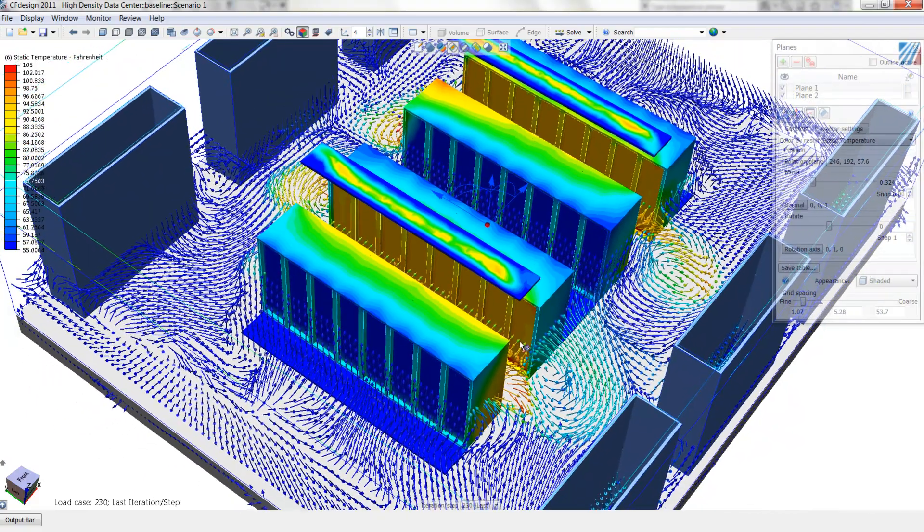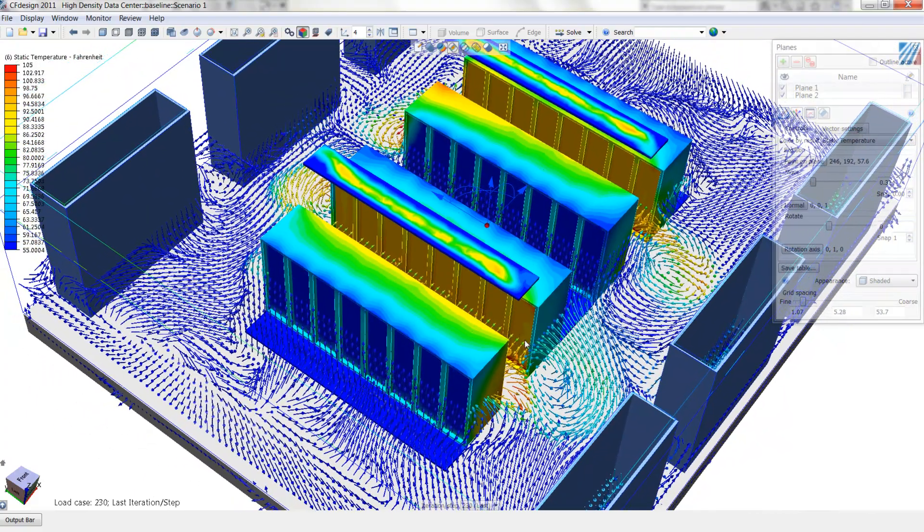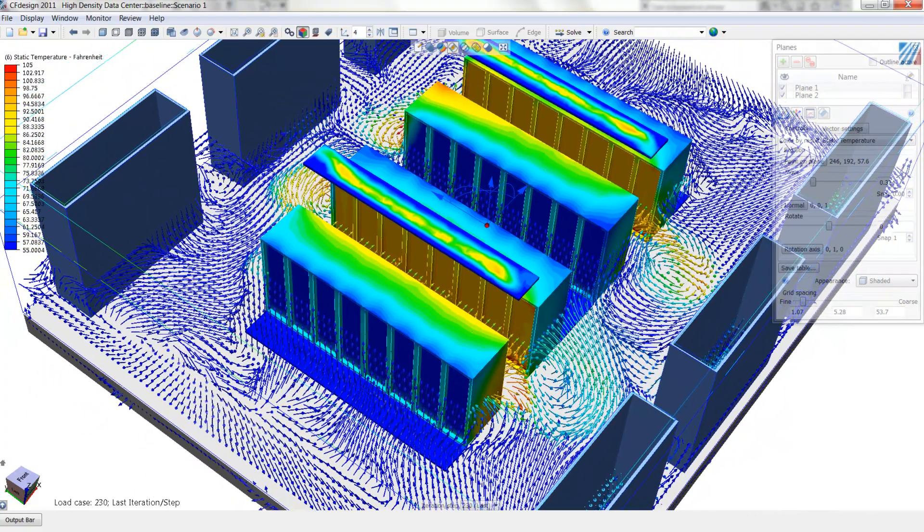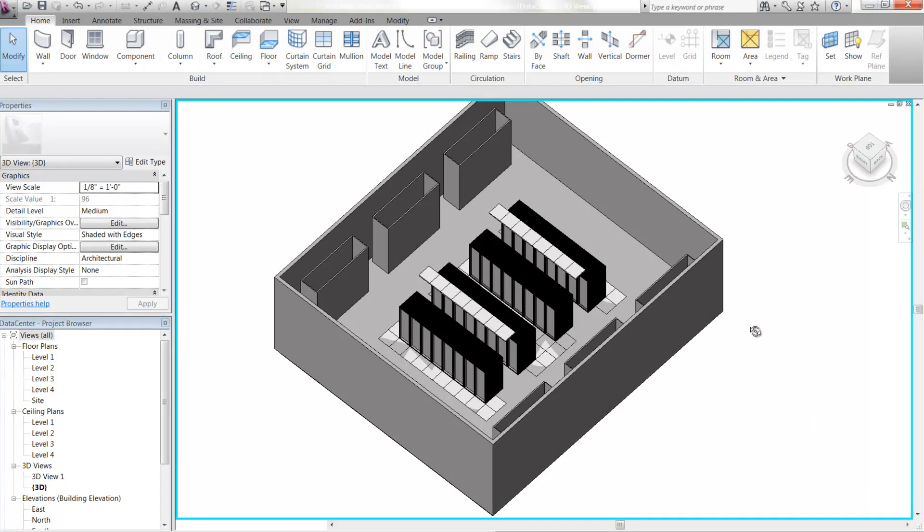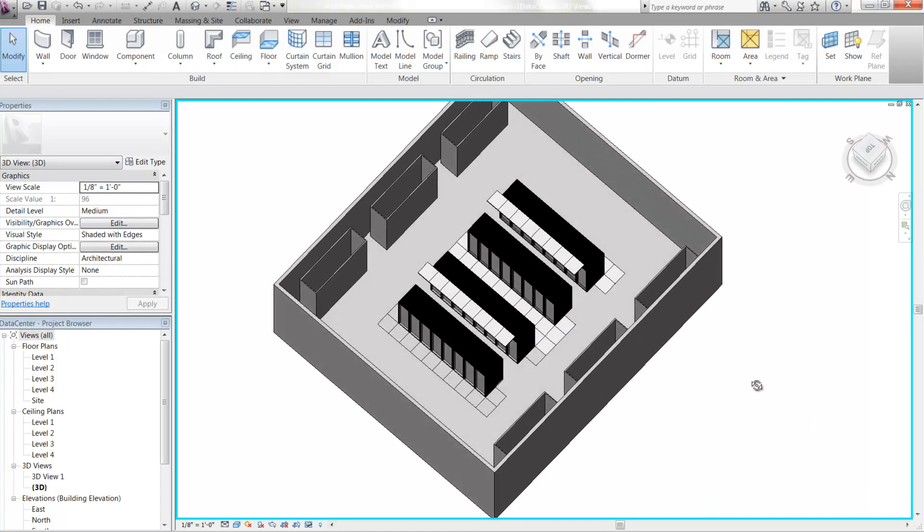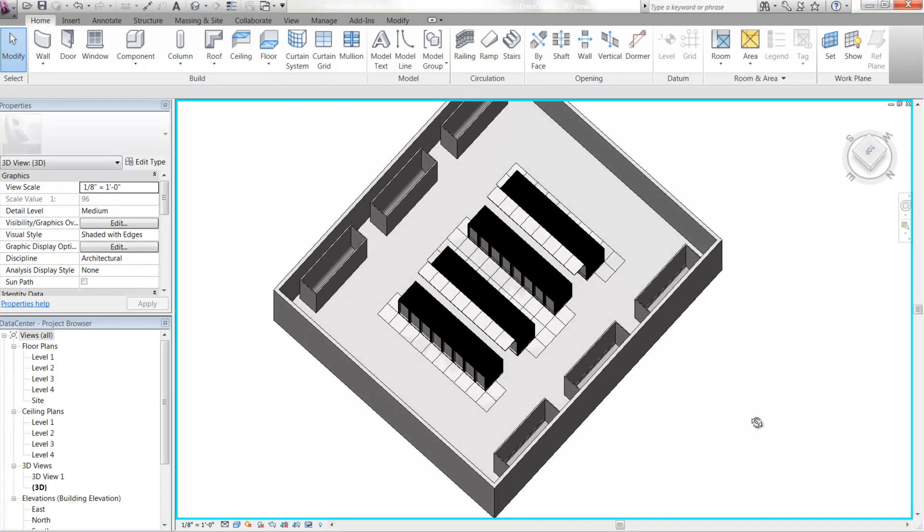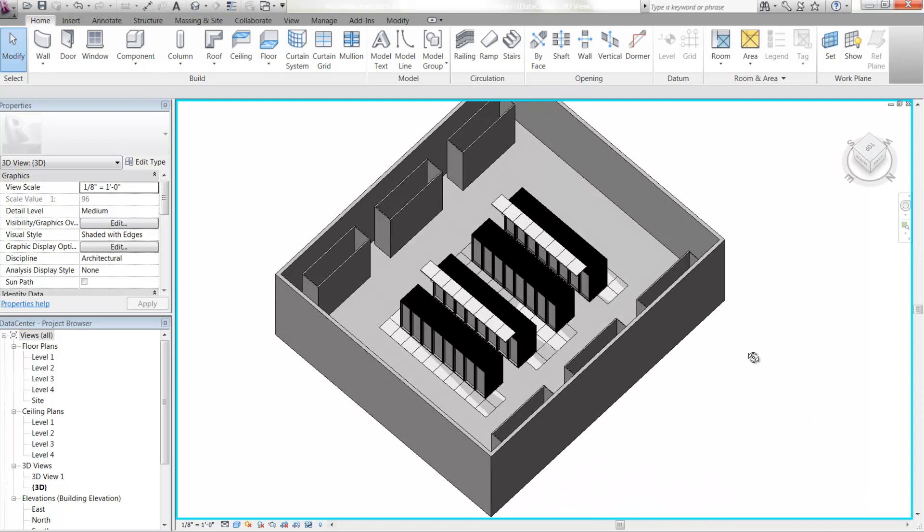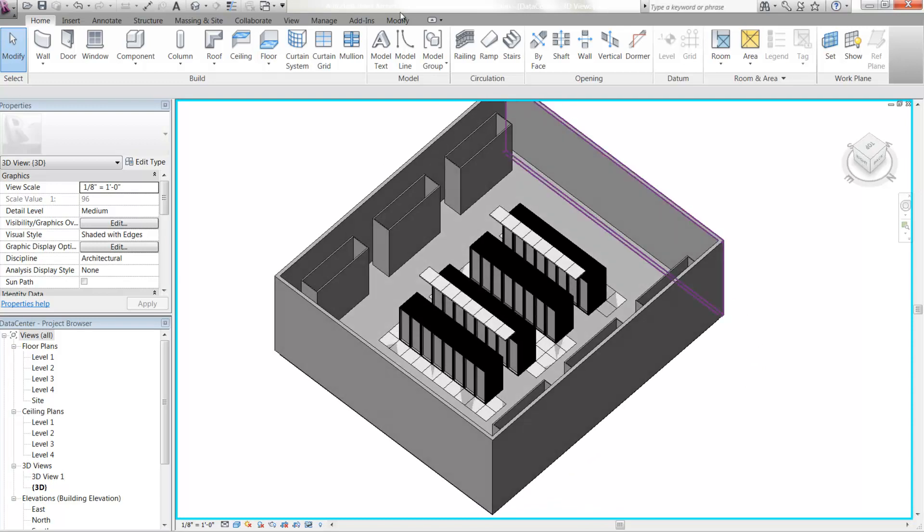One quick way to mitigate this is to add floor tiles or perforated tiles on the ends of the aisles to create an air curtain or air barrier. We've now added floor tiles. Let's pull this back into CFDESIGN for further analysis.